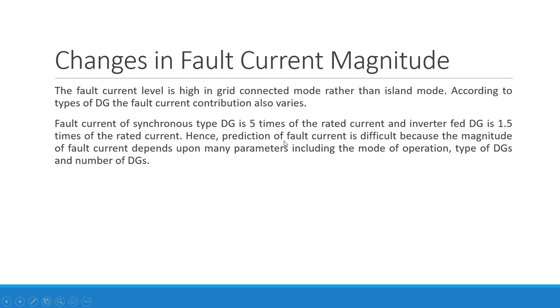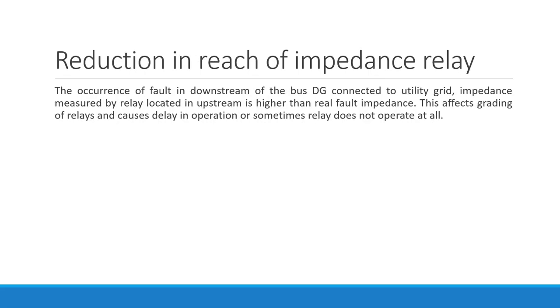Therefore, prediction of fault current is difficult because the magnitude of fault current depends upon many parameters, including the mode of operation, types of DG and number of DG. Basically what we are trying to understand here is that there will be a change in the fault current, because it depends upon various factors: in which mode the microgrid is operating, islanded or independent, which type of DG is there and how many DGs are there. So this is going to decide the fault current. That's why it becomes difficult to find the change in the fault current magnitude. We are talking about the protection scheme or issues related to the protection of microgrid. So this is the issue.